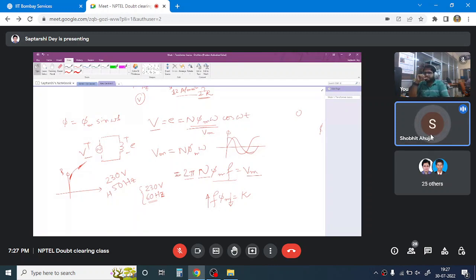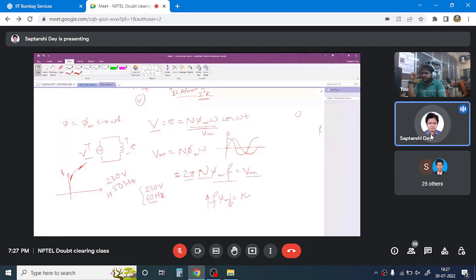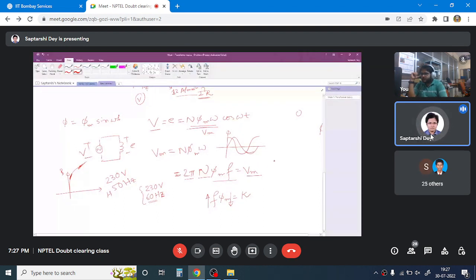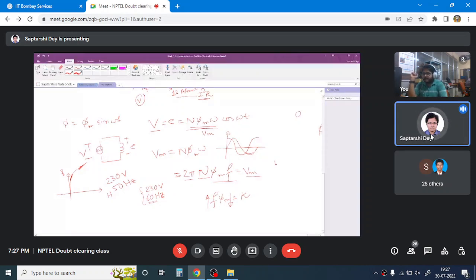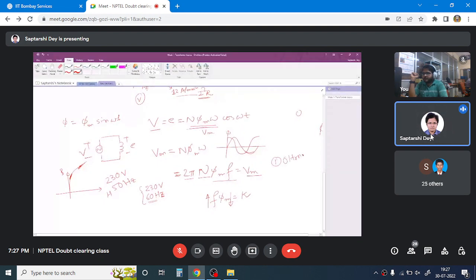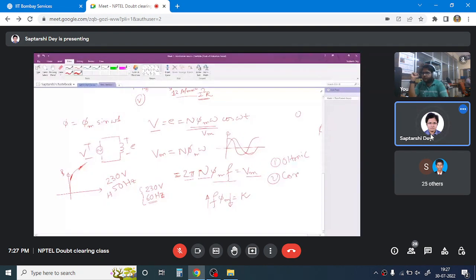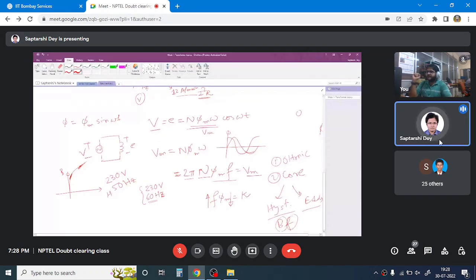Sir, what is the effect on the losses of the transformer? Losses in a transformer, there are losses like winding losses, which are not affected. Let us say you have limited the load in such a fashion that your winding current is not exceeding the rated RMS current. So ohmic loss is not changed. So there are two kinds of loss. One is ohmic loss, the other is core loss. Now core loss has two components. One is hysteresis loss, the other is eddy current loss. Now with increasing values of B and F, these hysteresis and eddy current losses will increase.